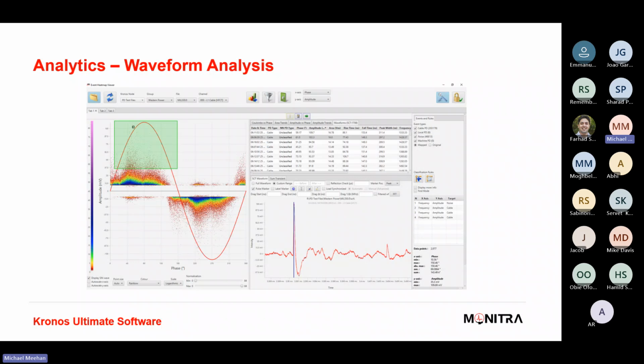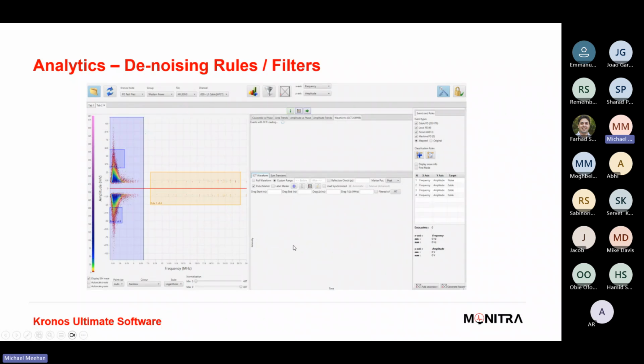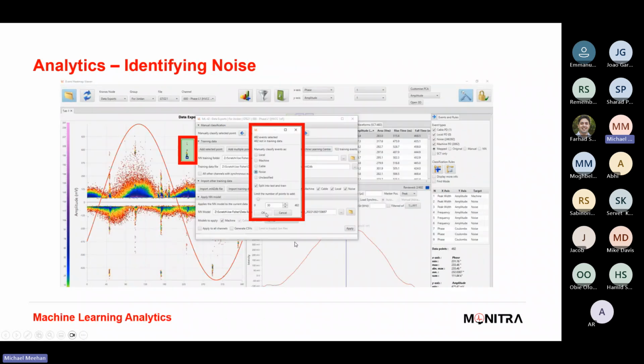And you're removing that human error factor, and you're removing that maybe go-to person approach, which can be a problem because if that person's not available, you've lost your whole asset plan. So the benefit of going towards a more, I guess, automated type of PD analysis, with the experts still looking at this, is that you get consistency in analysis, and you still have the experts in the background working on this, but they're magnified in the way that they analyze because they can run a set of machine learning rules first, and then use their expertise at the back end and really focus on what they're looking at and spend less time just filtering through the noise. So there's a lot of benefits by doing it this way in terms of being able to get that more accurate PD plot and that PD analysis back to the client, who is obviously keen to know the condition of their asset.